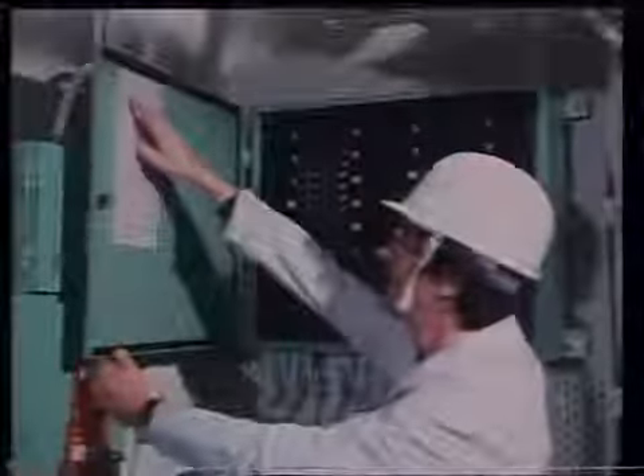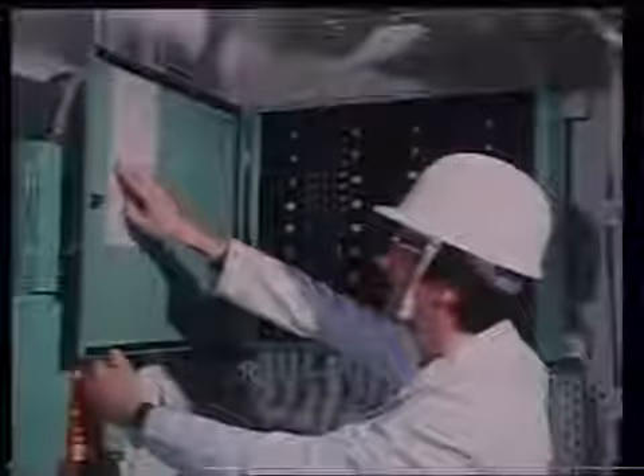The transformers will still provide the voltage of 220 or 110, as the case may be, but at a reduced power, at about 60% of rated output. This state is called the open delta connection. The supply voltage in a single-phase circuit on board ship with an insulated neutral electrical system is measured not between a line and a neutral, as on shore side, but between 2 lines.